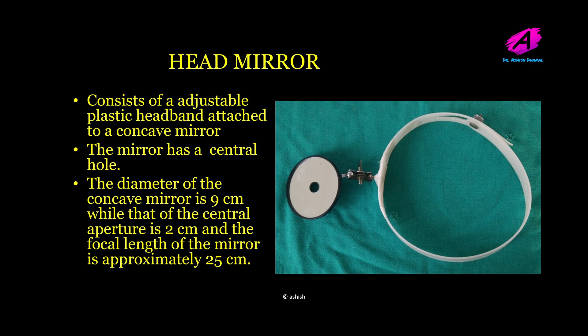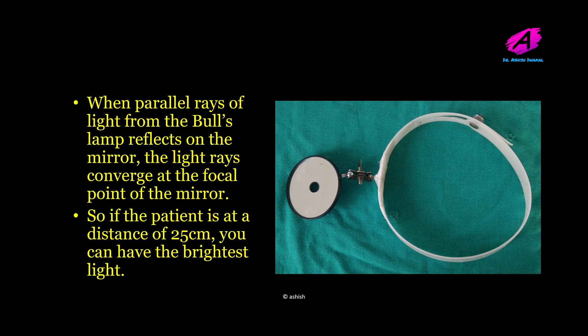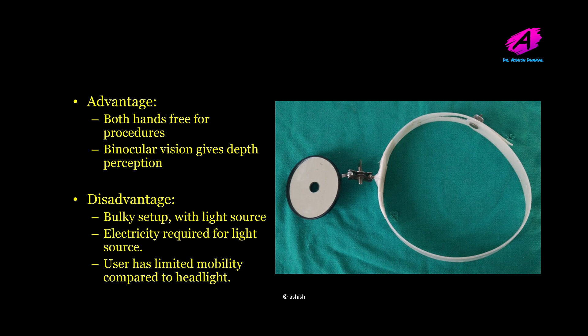When parallel rays of light from the bull's eye lamp reflect on the mirror, the light rays converge at the focal point of the mirror. So if the patient is at a distance of 25 cm, you can have the brightest light. Advantage of using a head mirror with bullseye lamp is both hands are free for procedures, and binocular vision gives you depth perception. Disadvantage, the setup would be bulky with a light source, and electricity is required for the light source. The user also has limited mobility compared to that of the headlight.